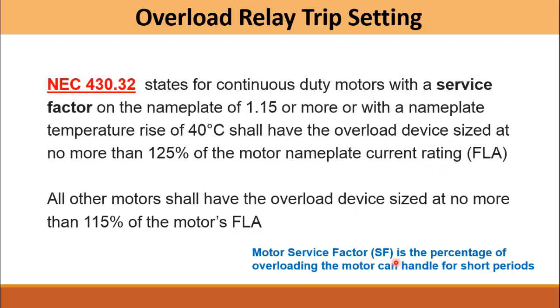The service factor is the percentage of overloading the motor can handle for a short period of time. So motors which are allowed to run at 115% of rated power are protected with an overload device sized at no more than 125% of full load current. All other motors with a service factor of 1 will have the overload device sized at no more than 115% of the motor's full load ampere.